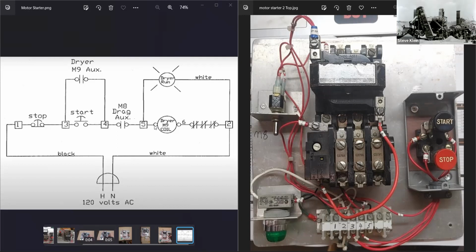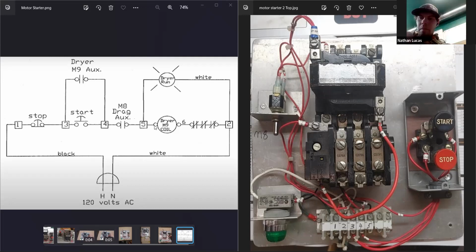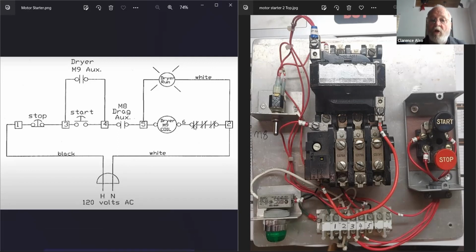And that's when you push the button down, is that correct? Yes. If I'm going to check the 6 side of the overload, when are you expecting the problem? When you push the start button down. You've got to troubleshoot this under the condition that it's not working. That's why you knew to check the 5 side of the coil, but you had a brain fade on the 6 side.